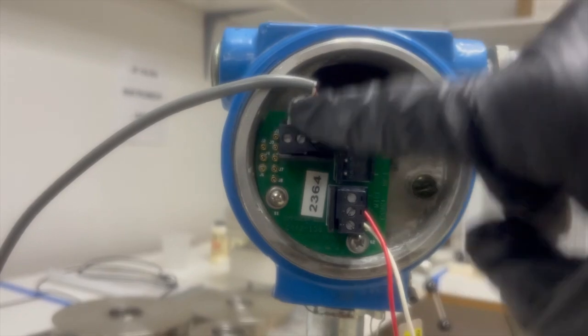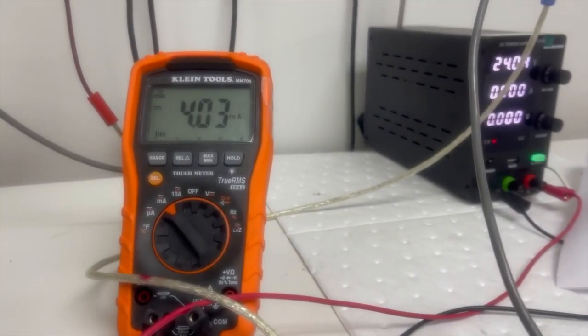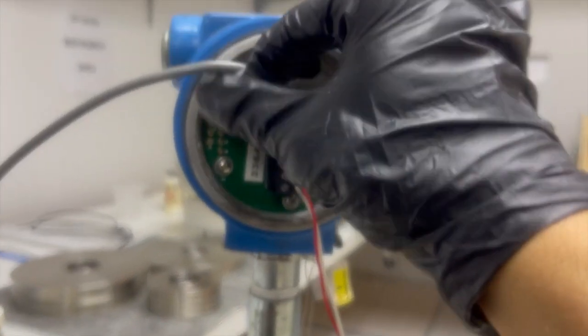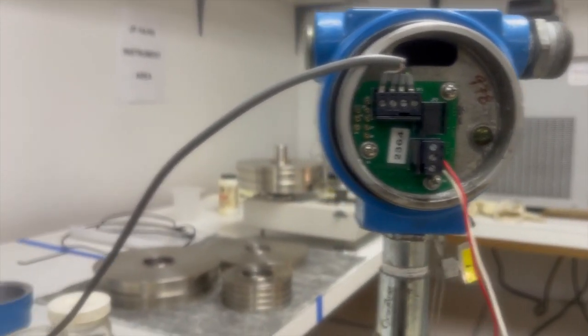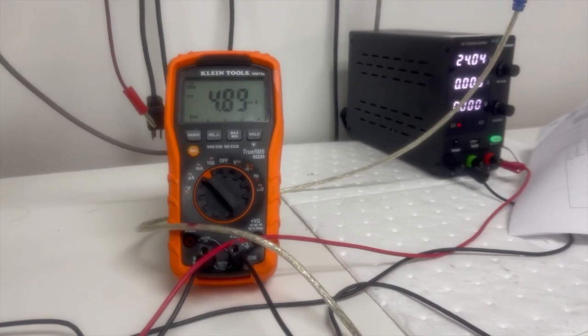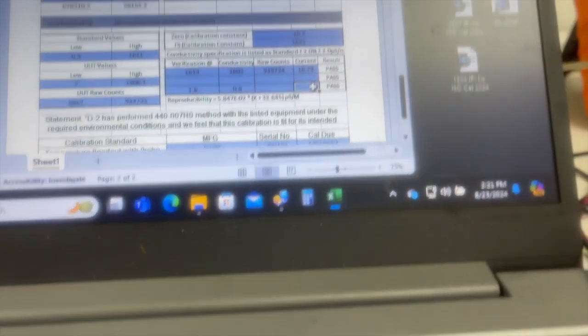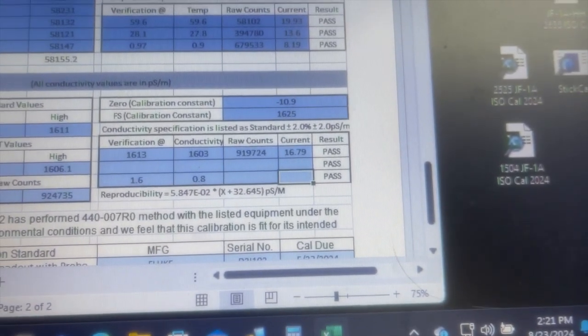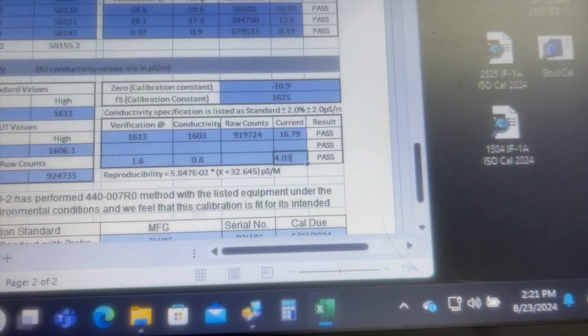Because we're in run mode, you can get the voltage, but to get the voltage at 0, you have to disconnect the serial port. Not 4.9, 4.03 is your actual voltage. So when I put that back on, you'll see it flies back up. So your actual voltage at that is 4.03.